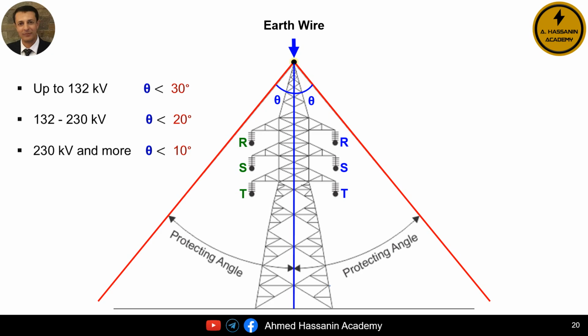For transmission voltages up to 132 kilovolts, the protection angle should be less than 30 degrees. For transmission voltages from 132 kilovolts up to 230 kilovolts, the protection angle should be less than 20 degrees. For voltages higher than 230 kilovolts, the protection angle should be less than 10 degrees.